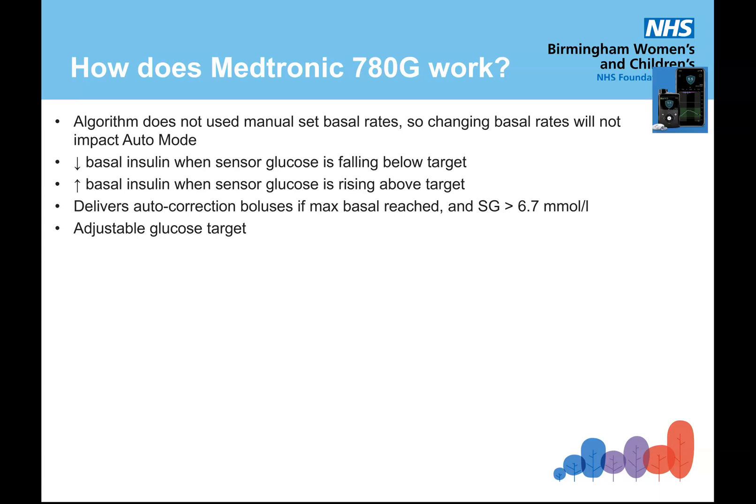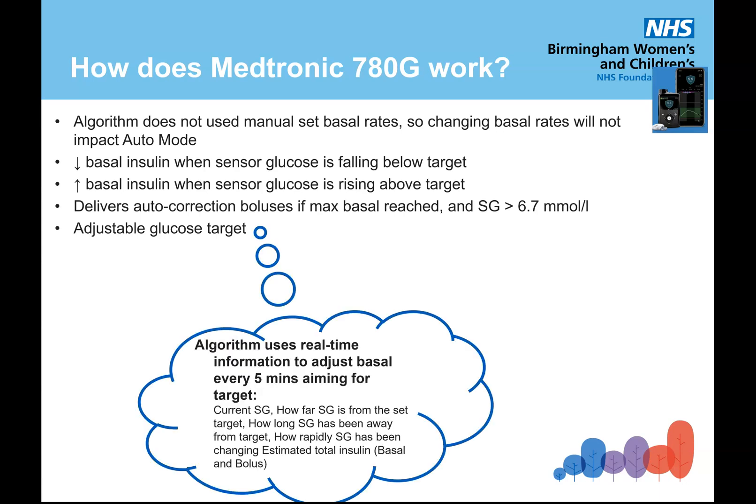When the glucose level is falling below target it will reduce the insulin; when it's going above target it will increase insulin. Importantly, this system is very aggressive at managing highs — it will deliver auto corrections if the max basal is reached and the sensor glucose level is above 6.7, and it has an adjustable target glucose level. It really looks at the current sensor glucose, how far it is from the target, how long it has been away, and how rapidly it has been changing to estimate total insulin. It doesn't focus on previous insulin on board or carbs — it's very glucose-centric, therefore it can be a lot more aggressive in tackling highs compared to other systems.